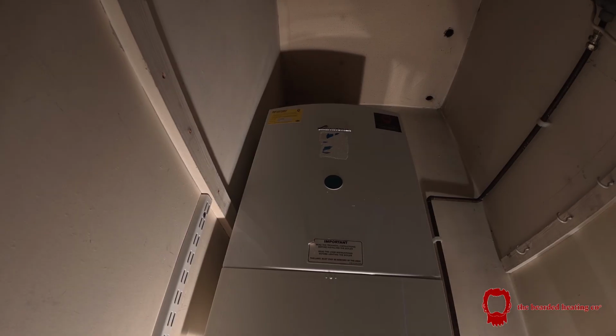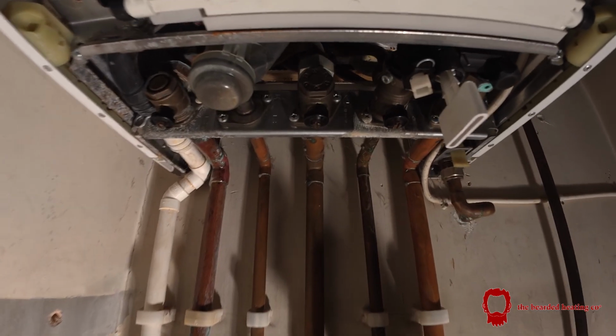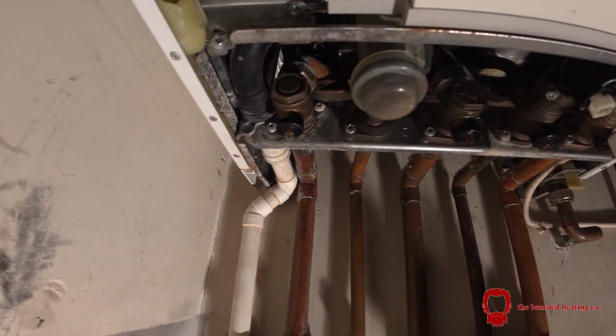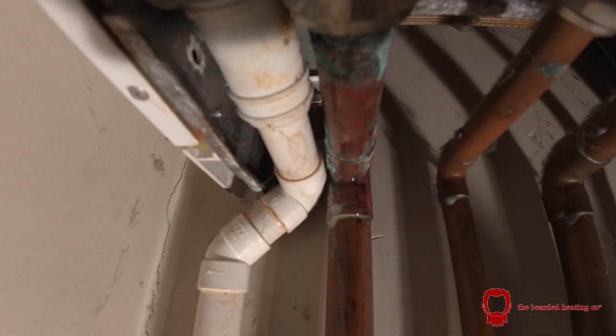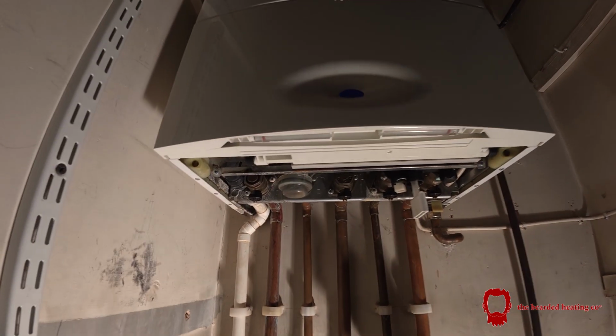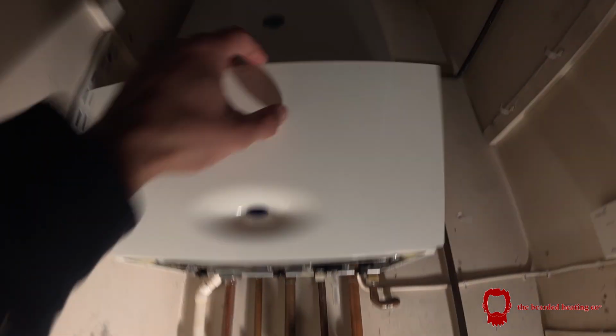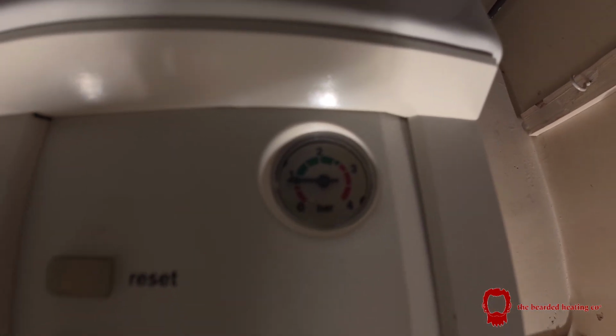This one is a call out. I was here a few months ago and the fan was gone, so I replaced the fan, and now I'm back because the customer reported it's leaking. Let's have a look. We're under the boiler, a Worcester Junior. Let's see what's leaking. Oh, there it is. It can only be the left hand block because the customer hasn't reported the pressure going down, so the pressure is still where it is. It must be the left hand block.